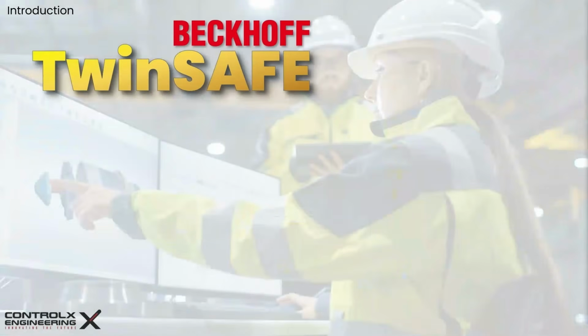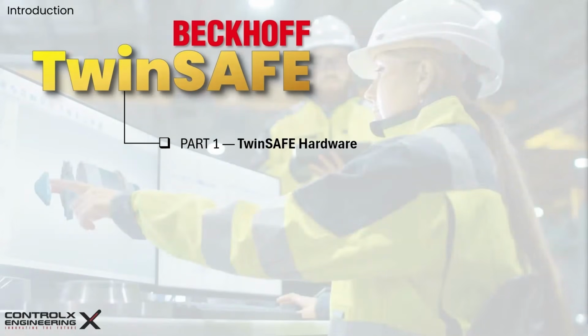To make sure you walk away with a complete understanding of implementing functional safety with TwinSAFE, I have broken this tutorial into a 3-part series. In today's tutorial, which will be part 1, we are going to deep dive into the TwinSAFE hardware ecosystem. I'll show you the difference between EL terminals for your cabinet and EP boxes for the field. We'll talk about the yellow architecture and how FSoE allows us to run safety data over standard EtherCAT cables without compromising on SIL 3 or PLE standards.